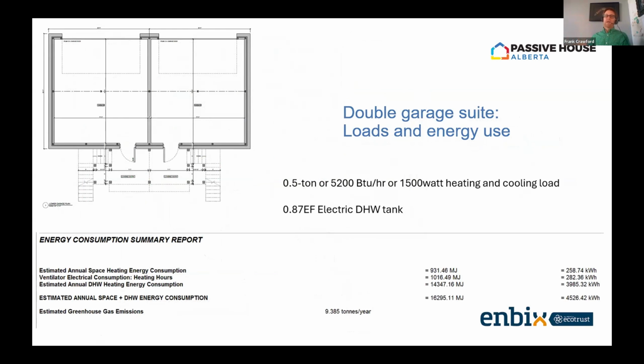We made this all electric, so we put in just a basic electric resistance tank. The interesting thing is that because the space is so small and high performance, roughly R40 walls, R40 floor, R60 roof, the actual energy use from F280 and HOT 2000 for space heating is 258 kilowatt hours, which at 20 cents per kilowatt hour is only $51 a year to heat this unit.